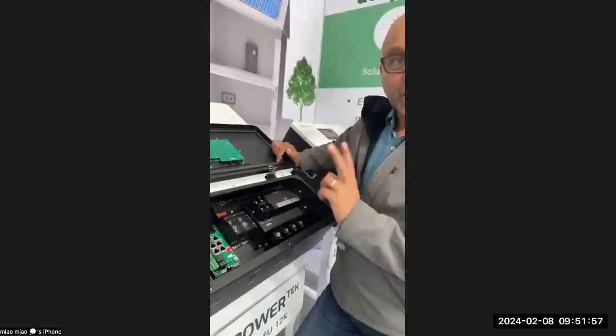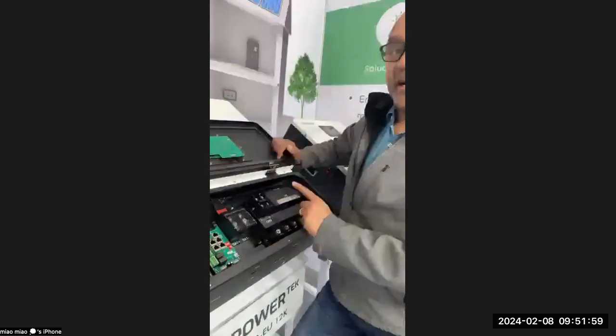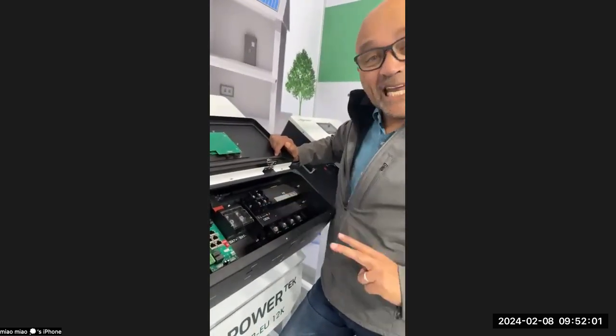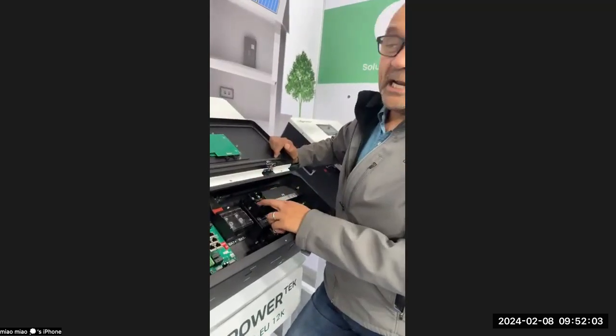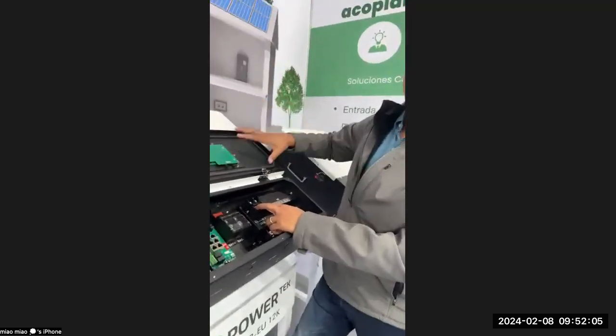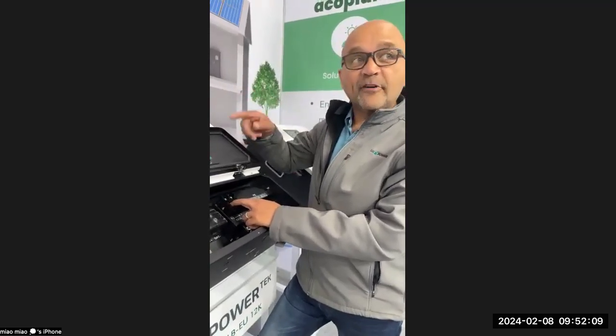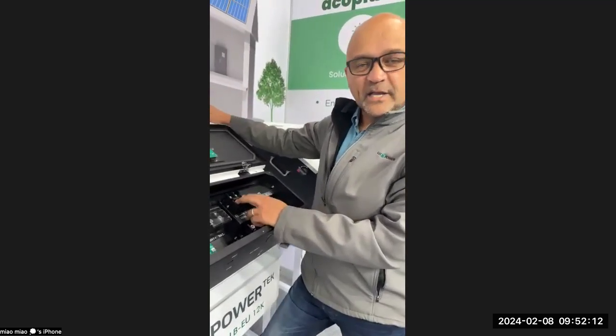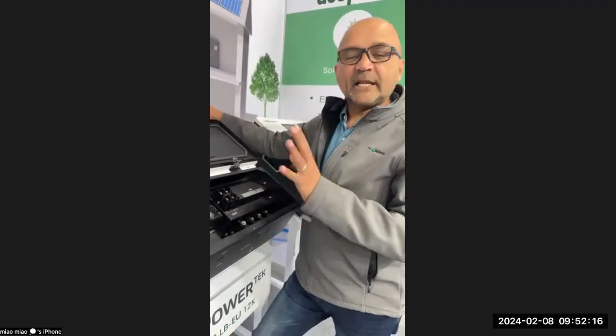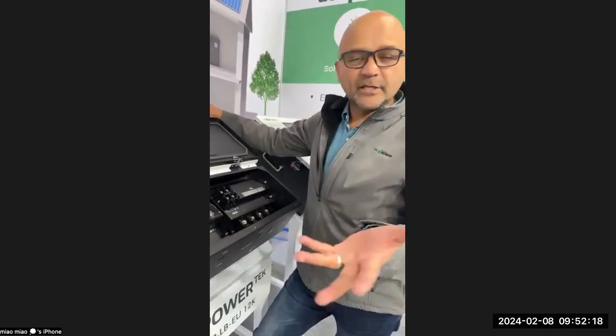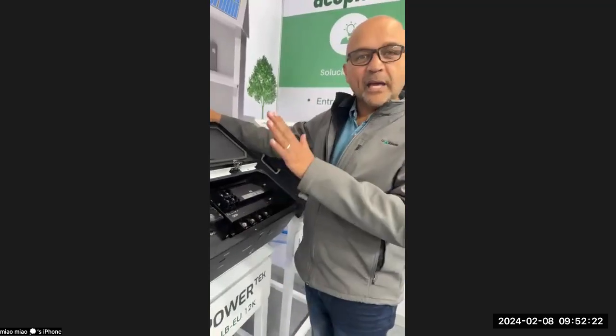So for the generator function, if you enable it as a generator function, then you can only use it as an input port. Means you can connect a generator to it. We always recommend that the sizing of the generator is 125% higher than the machine itself. So for a 12 kilowatt, you just go 12 kilowatts, add 125%. That'll tell you how big your generator must be. I'm going to just suck a number out of the sky and say 15 kilowatts. So a 15 kilowatt generator will be ideal on here.